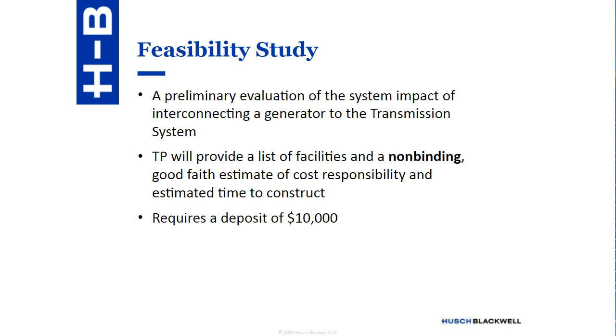The timing of the feasibility study begins at the point where there is a valid interconnection request. At that point, the transmission provider will provide a standard form of feasibility study agreement and a good faith estimate of the cost for completing the study. Before the study can begin, the interconnection customer must provide a deposit of $10,000 and any requisite technical data. From that point, the transmission provider will use reasonable efforts to complete the study in 45 days.